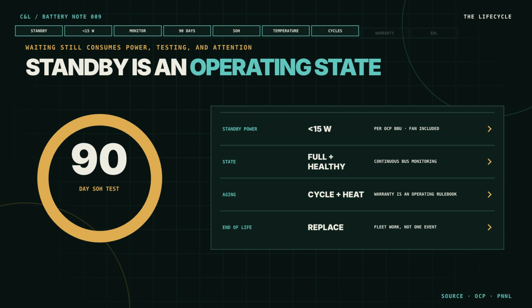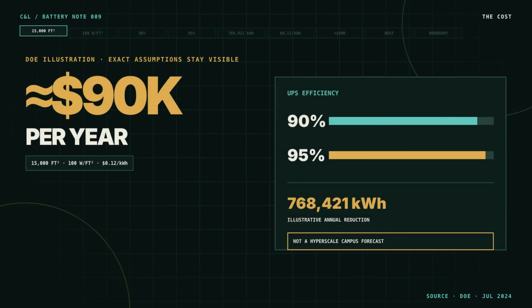continuous. The Pacific Northwest report adds another boundary. UPS batteries sized for tens of minutes can wear out quickly if they are used for continuous load smoothing. A battery warranty, therefore, is also an operating rulebook. Depth of discharge, temperature, charge windows, cycle count, and reserve margin determine what the asset is allowed to do. If a proposal counts grid revenue but ignores faster aging or reduced emergency reserve, it is counting the same battery twice. The battery may discharge rarely, but the UPS power path can operate every hour. That is where a small efficiency gap turns into a persistent bill.